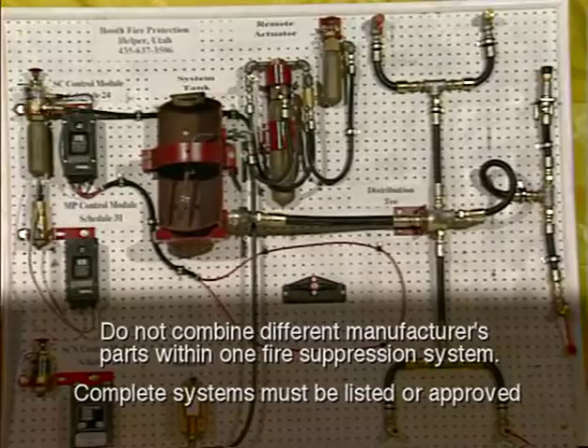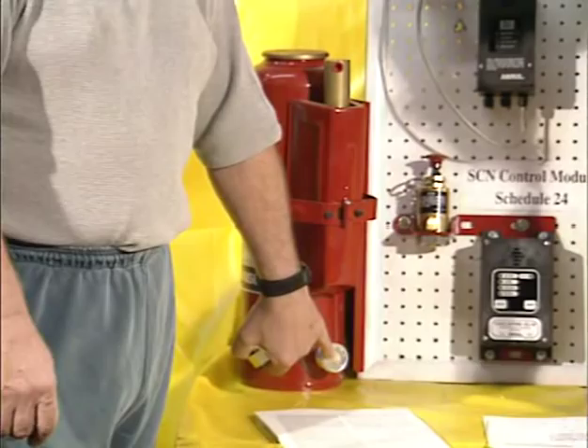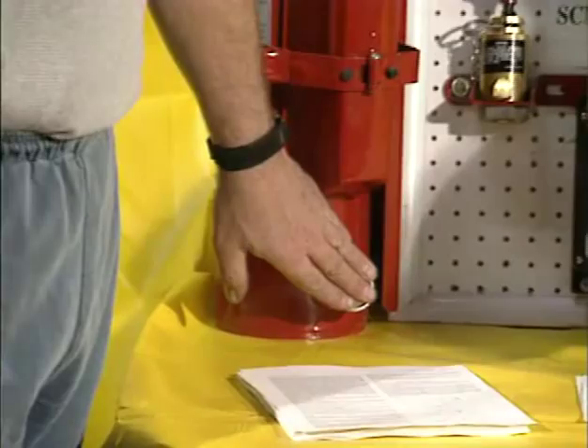We have an actual 20-pound pneumatic system — pneumatic means that the cartridge is mounted right on the tank itself. This bursting disk union on the tank should be hand-tight, snug only. On the inside you have your bursting disk, which holds the chemical in until the system is ready to fire. On the outside there's a plastic ring that needs to be against this shoulder fitting — it prevents it from falling out.